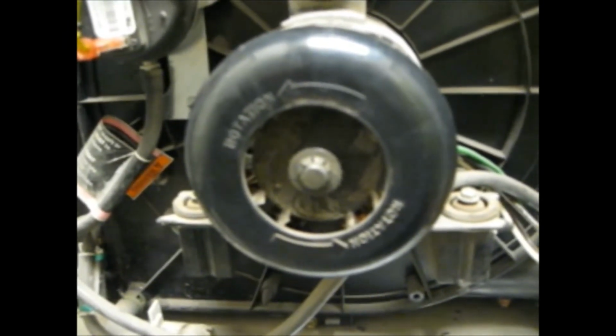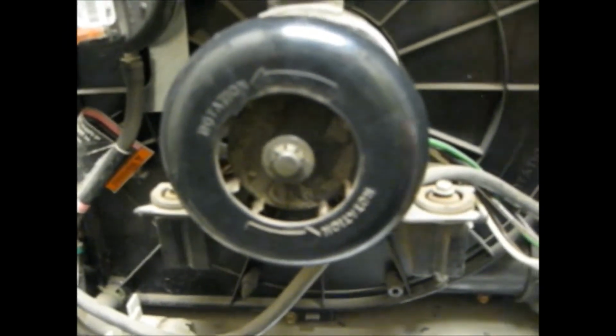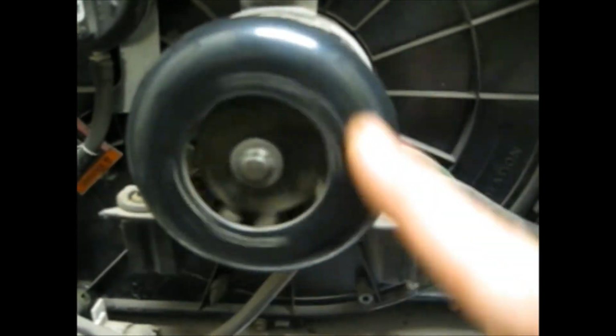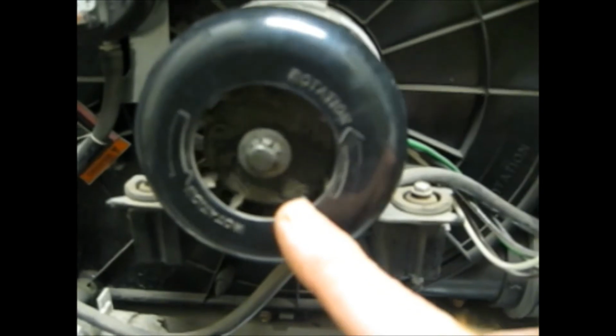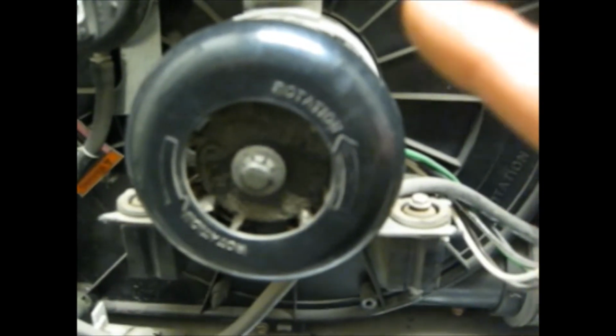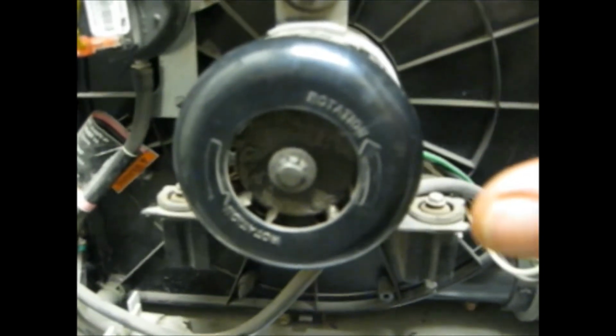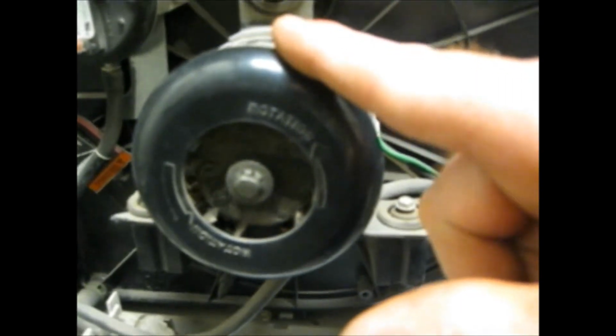The next thing to check is your inducer motor. This is the one that has to spin. It's usually the first thing that happens in the process of starting your furnace. One of two things could be bad. One, your inducer motor could be bad, or the capacitor for the inducer motor could be bad.